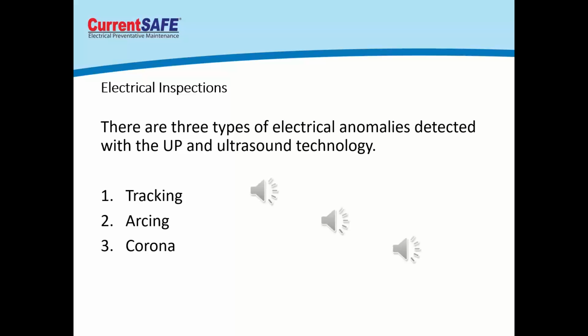The next thing to build up after that in a low voltage distribution system is a direct short. So arcing and tracking are the early warning signs that we're building towards a direct short circuit to ground or phase to phase. It could be either or. So this is a great way to let a customer know, hey, we do hear something, and the eventual failure of that component is based on the severity of arcing and tracking. How close are we? How much arcing is going on? Because arcing means that the path is already built. Now we're just trying to build a constant path versus a temporary path. And once that happens, we'll have a fault condition and a short circuit, and the equipment will fail.